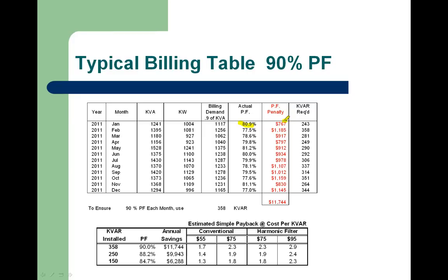On that particular month, we're paying $767 in penalties, and to eliminate those penalties, that particular month would need 243 kVAR. Now you'll notice that each month the amount of kVAR changes. Same thing with the penalties, and a lot of that has to do with the demand from the site over a period of a month. So in this particular case, one would require 358 kVAR to eliminate $11,744 in annual power factor penalties.